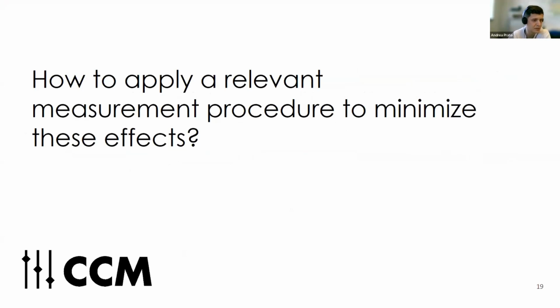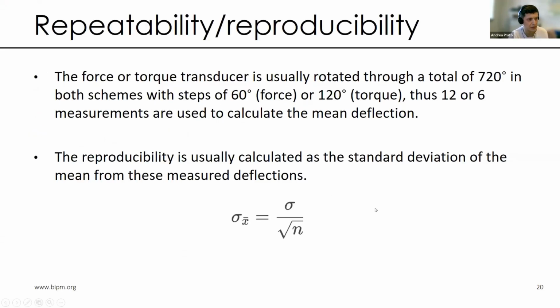So the idea in this second part is to show how these effects can be minimized during the key comparisons. First of all, we talked about repeatability and reproducibility, which are, of course, random effects related to the transfer standard itself. And this should be minimized because we want to verify the CMC of our primary standards at an uncertainty level depending on the generated known reference force or torque value.